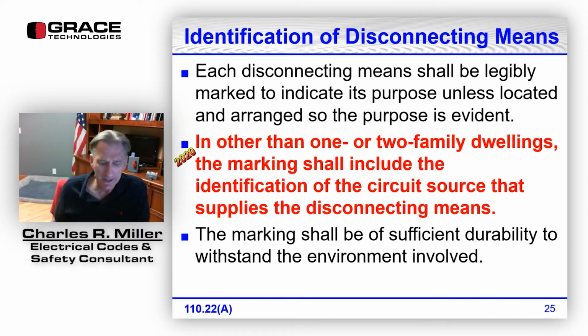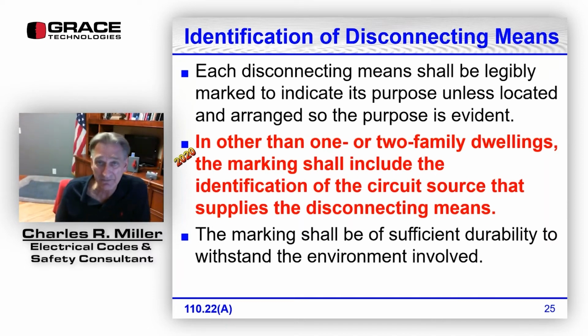And so this helps with NFPA 70E. It helps with electrical safety in the workplace. And of course, when we're complying with 70E, we shut off the disconnects. We have to do things like live-dead-live testing. We have to test for the absence of voltage and put the equipment into an electrically safe work condition.